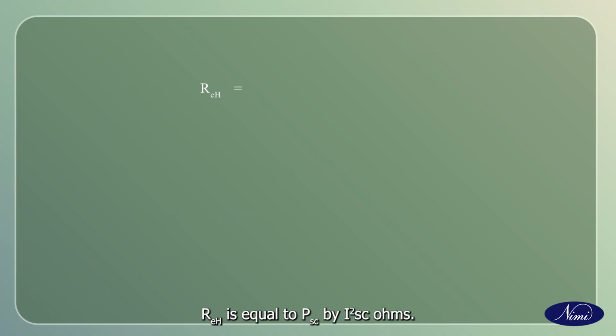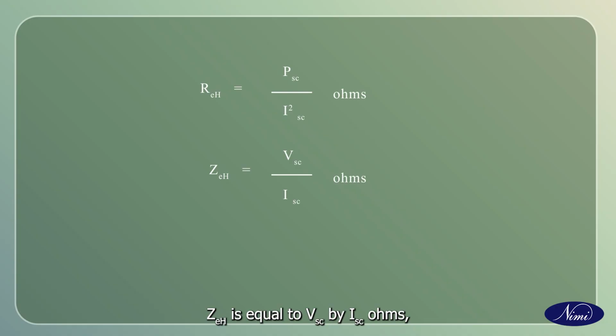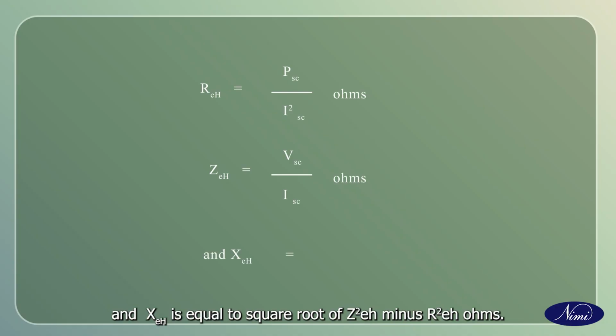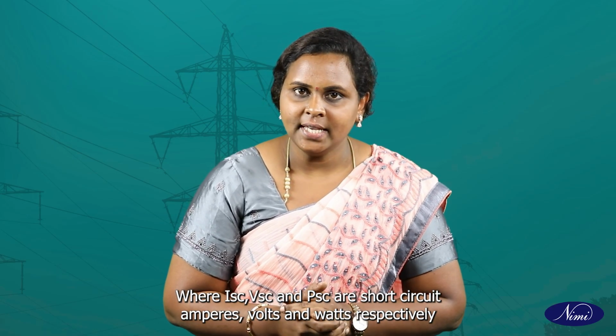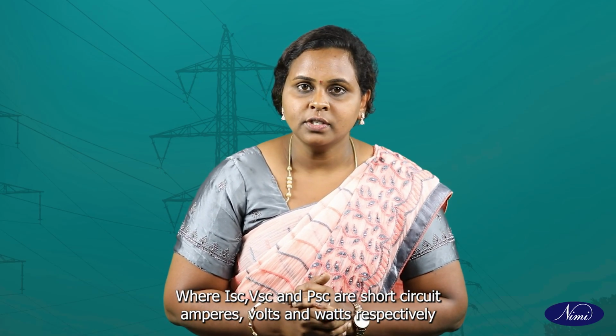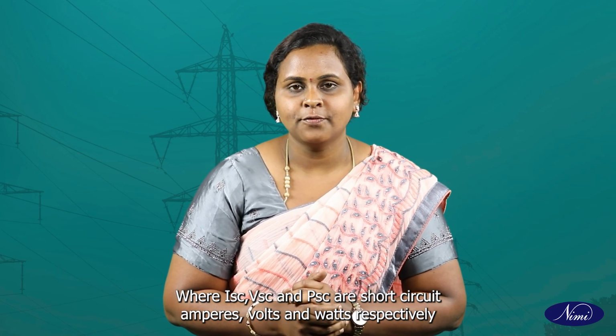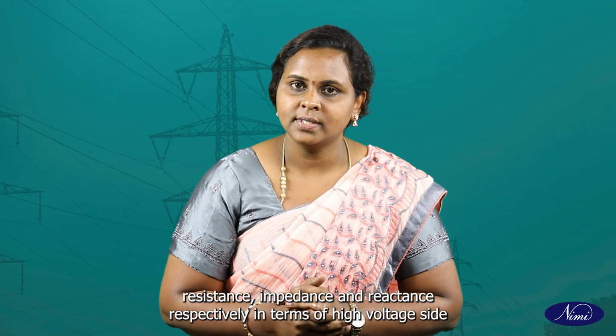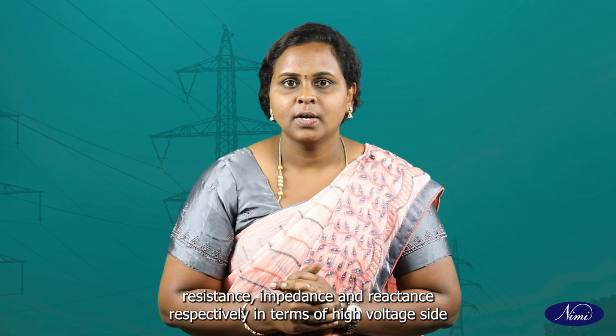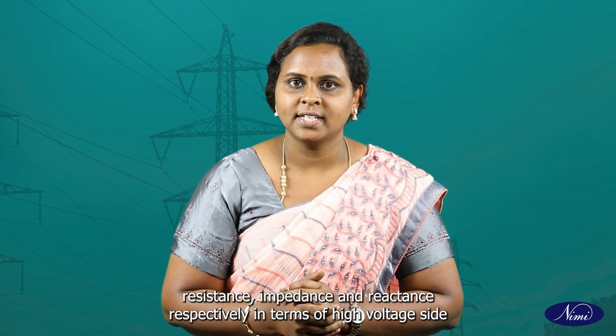Reh is equal to PSC by ISC square ohms. Zeh is equal to VSC by ISC ohms, and Xeh is equal to square root of Zeh square minus Reh square ohms, where ISC, VSC and PSC are short circuit amperes, volts and watts respectively, and Reh, Zeh and Xeh are equivalent resistance, impedance and reactance respectively in terms of high voltage side.